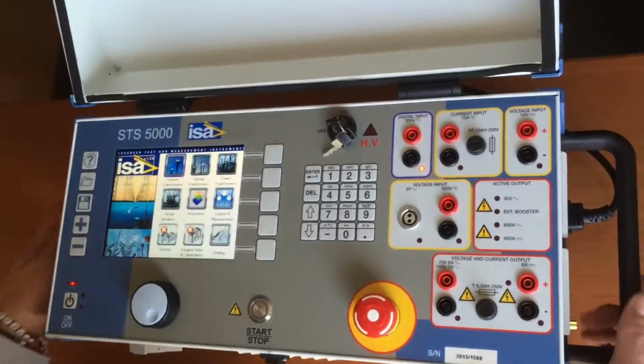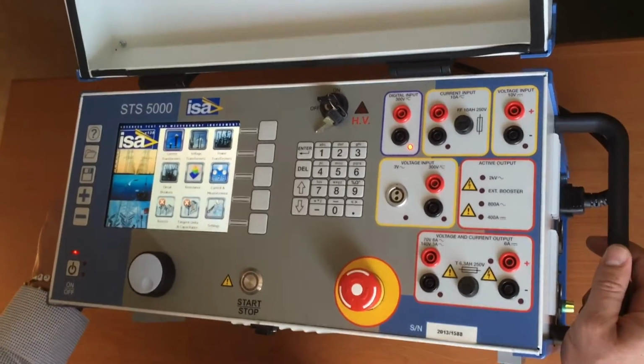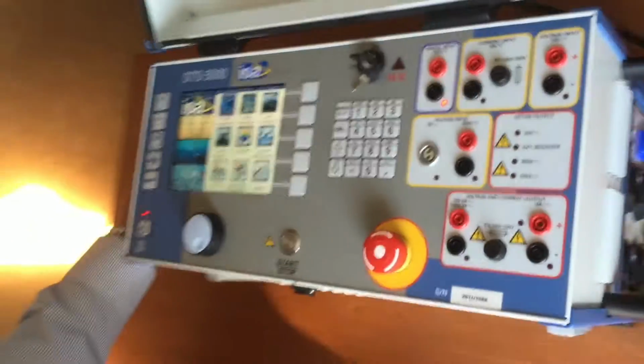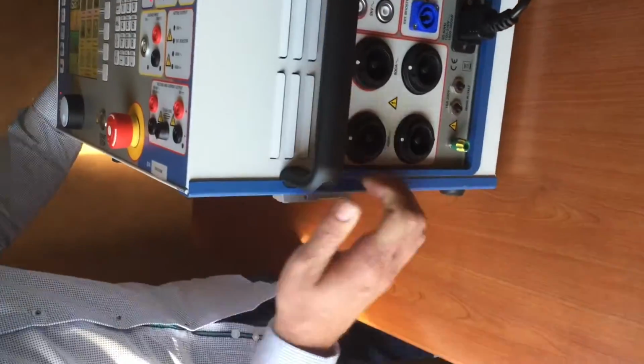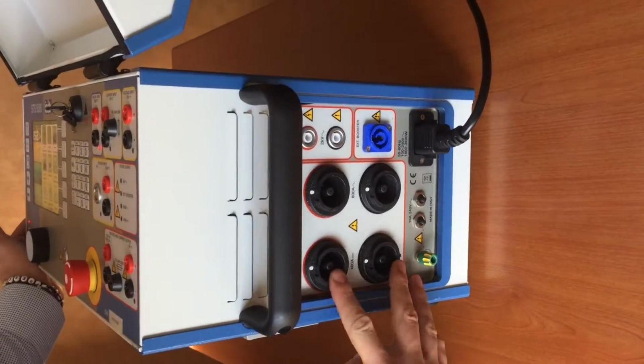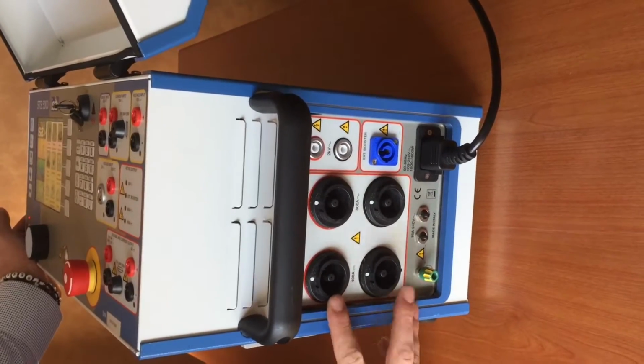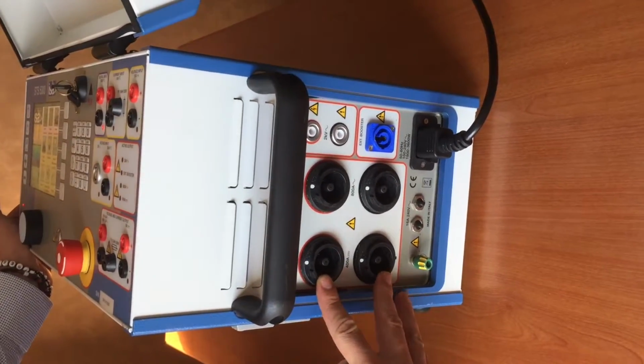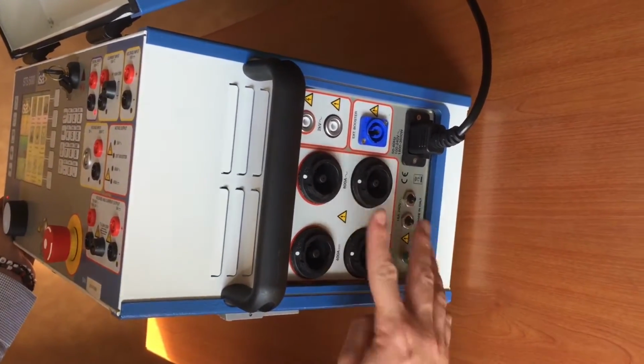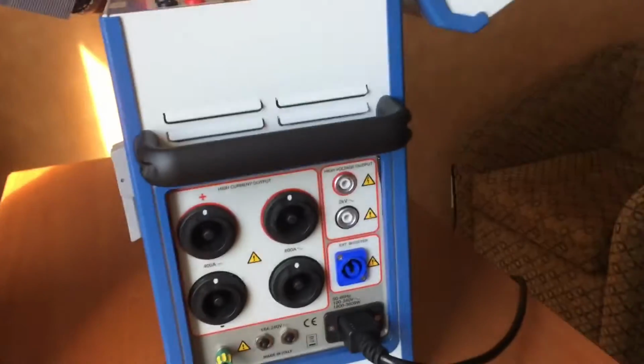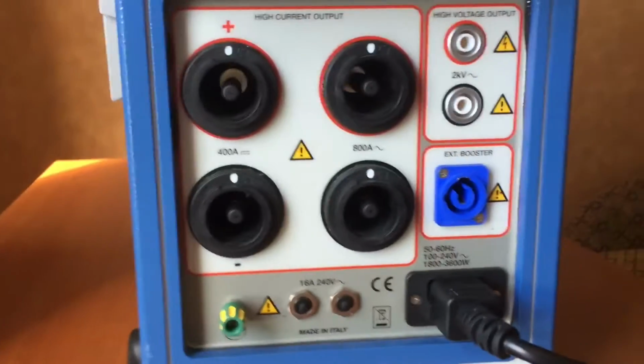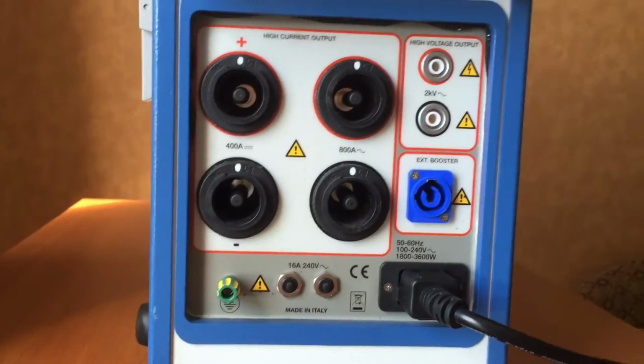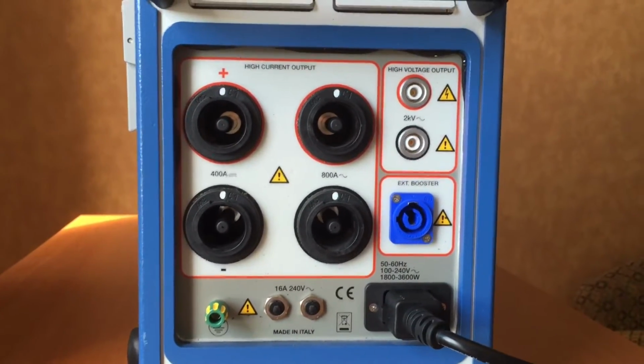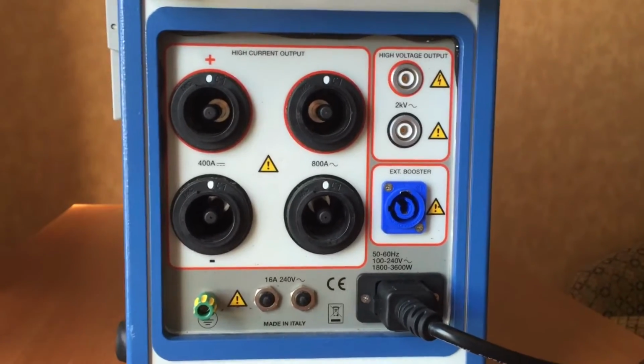STS is a multifunctional test set with a lot of inputs and a lot of outputs. So we'll start with the high voltage and high current outputs. Here you can see special connectors for 400 volts, 400 amps DC output, which can be used to measure resistance, or 800 amps AC output, which is usually used to test the ratio of a current transformer, or even maybe to trip a circuit breaker to monitor how much time it will take for it to trip.